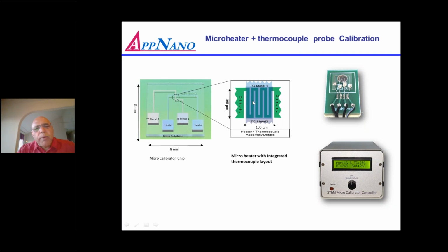So the close-up of this is shown here, where there is a heater and the thermocouple material is basically laid down on top of the heater. So now this thermocouple is getting heated with this heater. So we take a calibrated thermocouple and we calibrate this thermocouple with that heater, and now this is ready for testing and calibrating the thermocouple probe. So this is basically a three-step calibration. You have this calibrated thermocouple and integrated heater assembly, and then you use these two in conjunction to calibrate your thermocouple probe. The whole process of calibration takes 5 to 10 minutes, but it looks more elaborate here. But it's very convenient to use.